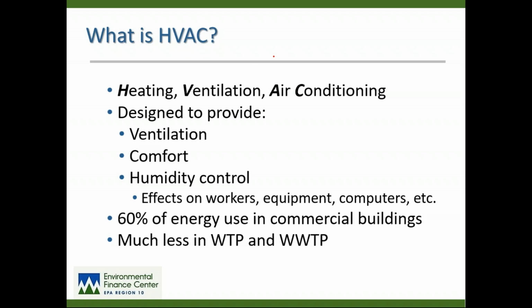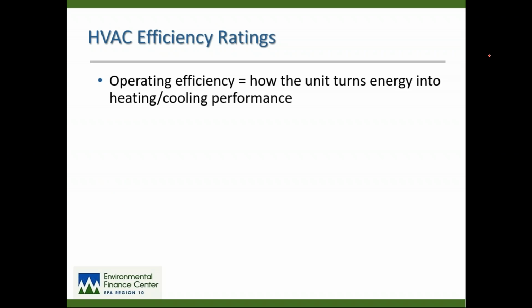So let's talk a little bit about HVAC. I want to wind up ahead of the top of the hour so that we can get time for some Q&A. You'll see that acronym HVAC, that's heating, ventilating, and air conditioning. It's designed to provide comfort, humidity control for equipment, humidity control for ourselves. In commercial buildings, it's a large percentage of energy use, but in water and wastewater treatment plants, really much less. Pumps and motors are really what's gobbling up the energy in our water and wastewater plants.